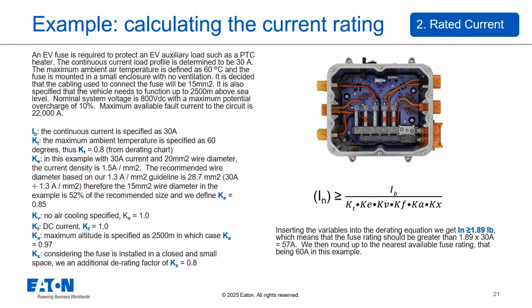Maximum altitude is 2,500 meters. Nominal system voltage is 800 volts DC with a potential 10% overcharge. Maximum available fault current is 22,000 amps. Okay, let's apply the factors we just talked about. I sub B is our 30 amp continuous current.